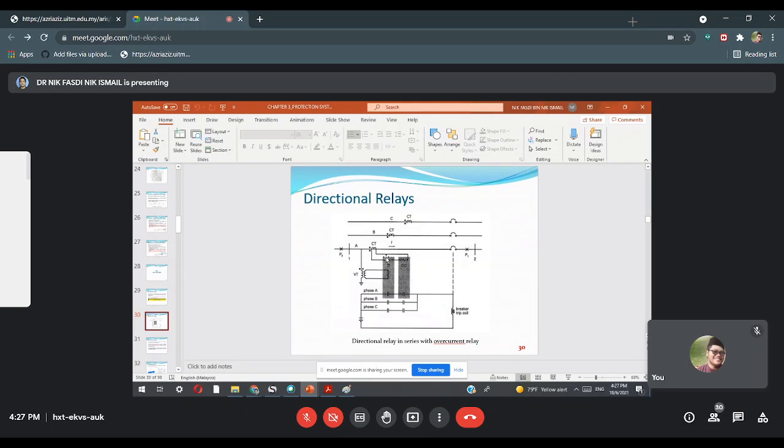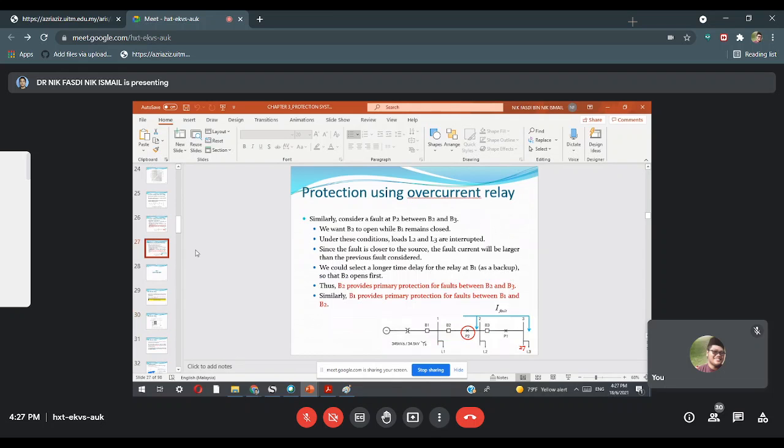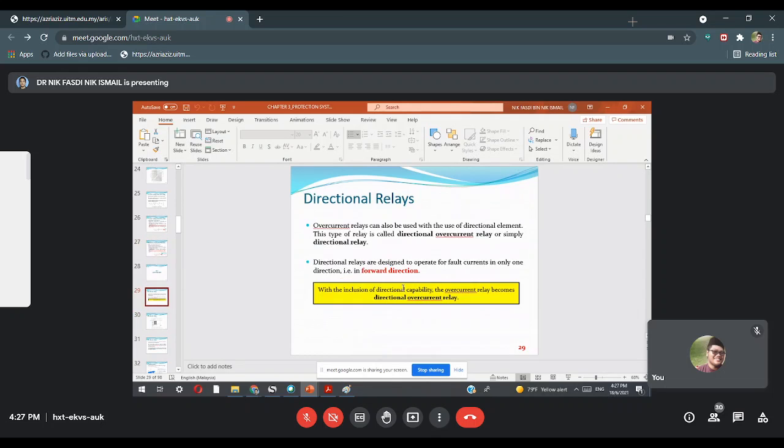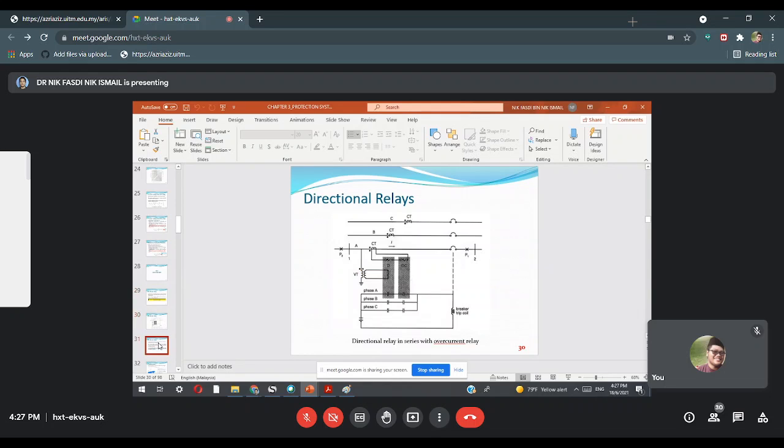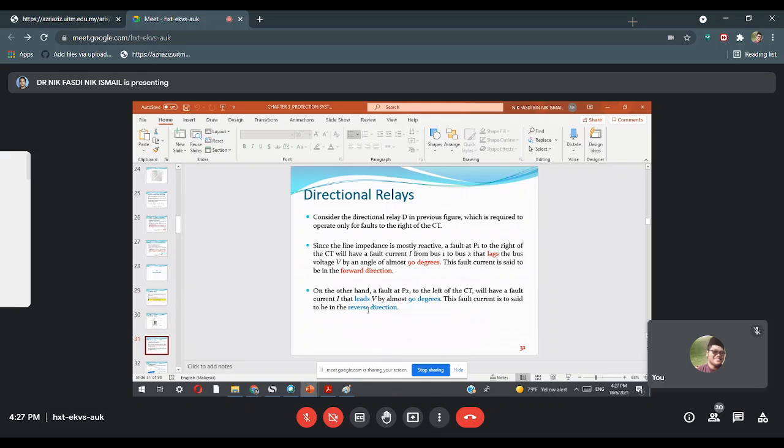Kalau jadi positif macam mana? You letak satu current transformer kat sini and current flow from the generator to the load, so dia akan jadi forward. Dalam case ni, again, I cakap is reverse direction. Okay, kat sini ada explain forward and reverse. Boleh faham forward and reverse?